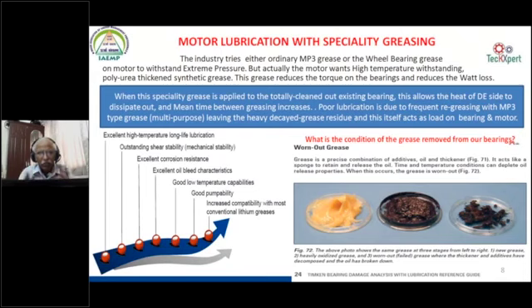Some industries have gone a step ahead. But it is all again the costing, the initial costing. Everyone thinks I will pay for only 1 kilo, only 100 rupees, 150 rupees, 200 rupees. It is not correct. Don't look at it that way. You can increase the mean time between re-greasing. If you go for a specialty grease, you don't need to touch your motor for more than a year. Previously, you were doing it every month or every 3 months. Now you don't need to touch the motor for 1 year, if the motor is done with a specialty grease.